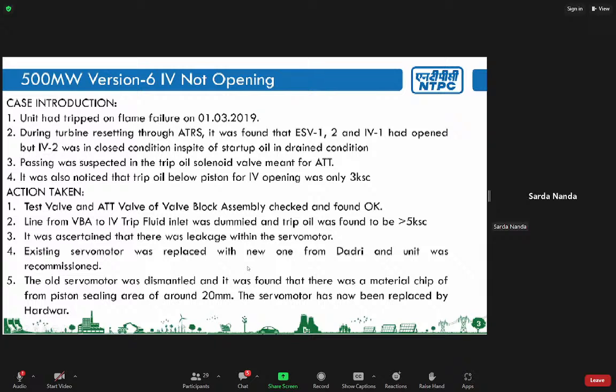We went downstairs to 8.5 meters. We tried to open the valve through our test valve, but even manually it did not open. Then we tried several things, one of which was a solenoid valve meant for ATT, installed in the valve block assembly. We replaced that also, but still it did not open. The trip oil pressure below the piston still remained 3 KSC, which is not at all sufficient for opening the valve. Then we opened the valve block assembly, the test valve and the ATT valve. We checked the clearances between the test valve and the ATT valve with the pilot valve and the liners. It was all okay.